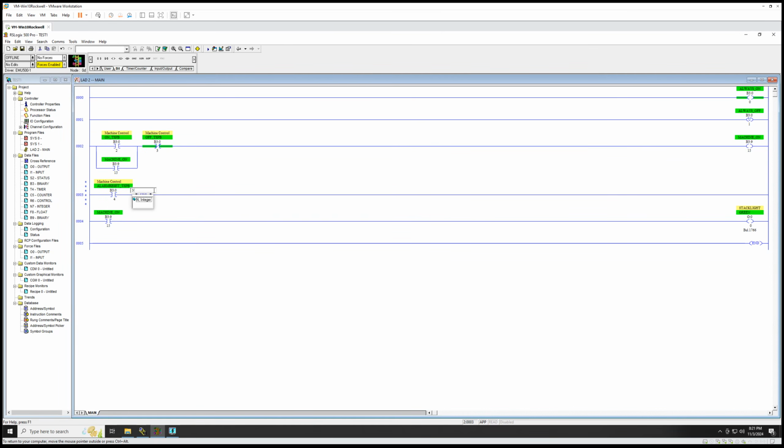And now here, if I do in, yes, the first one shot bit is used here. Now we need something towards the end of it. So what we'll do is create a pulse, the alarm reset pulse. That's what we'll call this. We'll use the next available B3 bit and call it alarm reset pulse. There we go. And we can compile everything now.